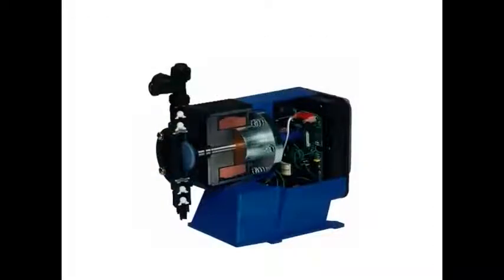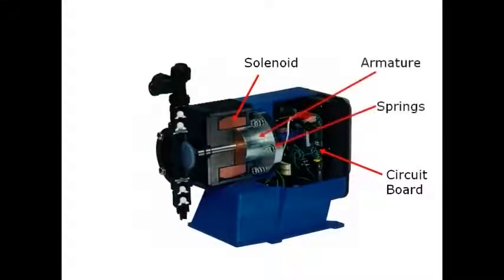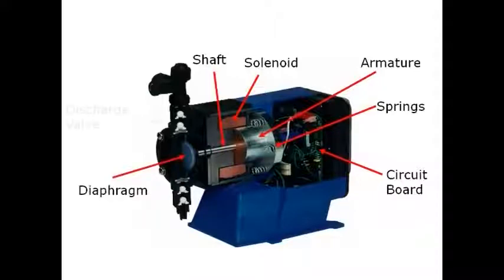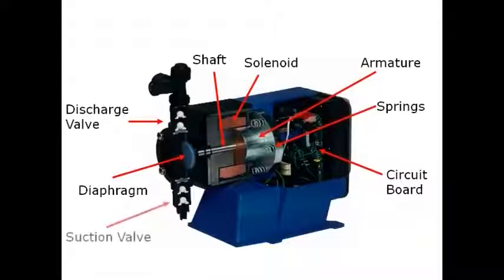The Pulsatron series pump is classified as an electronically driven diaphragm pump. The circuit board supplies a voltage to the solenoid, which generates a magnetic field. This pulls the armature forward against the spring tension. This also pulls the shaft forward, which has a diaphragm connected to it. The diaphragm displaces the fluid in the head through the discharge valve. When the solenoid is de-energized by the circuit board, the magnetic field collapses. The diaphragm and the armature return to the original position under the force of the springs. This action draws the fluid into the suction valve and the cycle repeats.